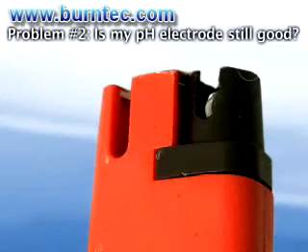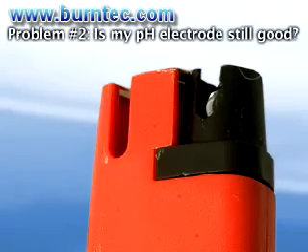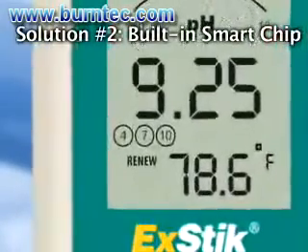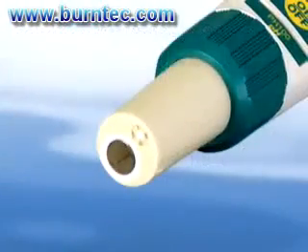Problem number two: uncertainty of not knowing how long the electrode will last and also the shelf life of storing an electrode. Solution: the built-in smart chip alerts the user when to replace or refill the ExStik pH electrode. A renew indicator will appear when the meter senses the electrode not delivering optimal performance.